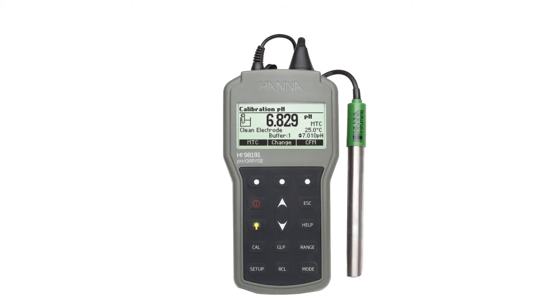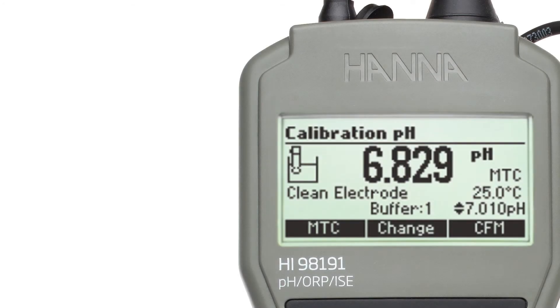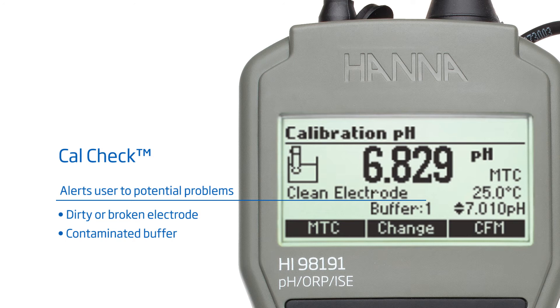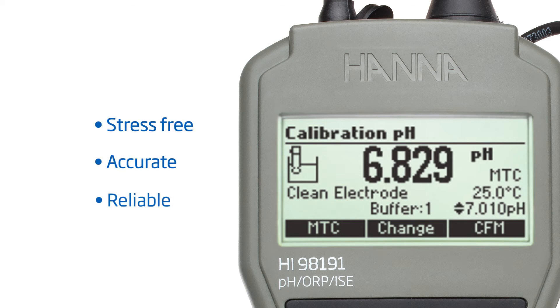The Hanna HI98191 Professional Waterproof Portable pH/ORP/ISE Meter is equipped with Hanna Instruments' exclusive CalCheck feature. CalCheck monitors electrode behavior over time and uses this data to alert the user to potential problems, such as a dirty electrode or contaminated buffer solution. The overall electrode condition is displayed on the measurement screen following calibration. CalCheck ensures stress-free, accurate, and reliable measurements.